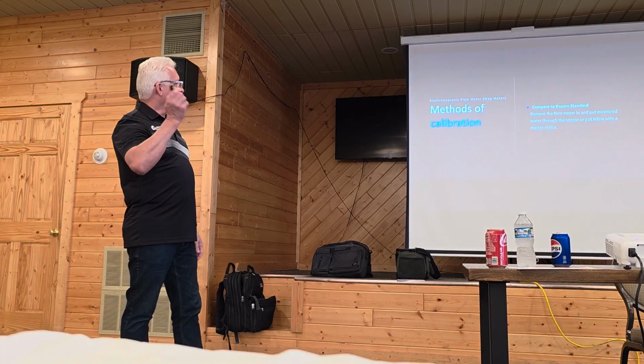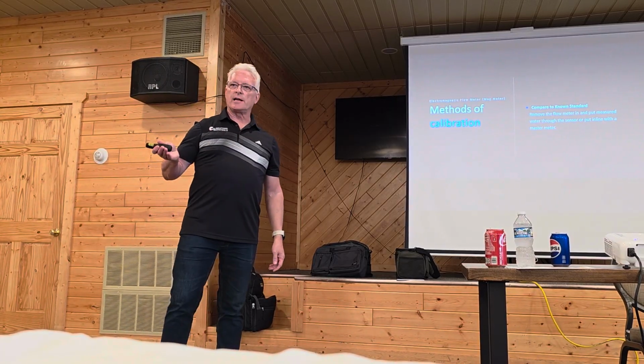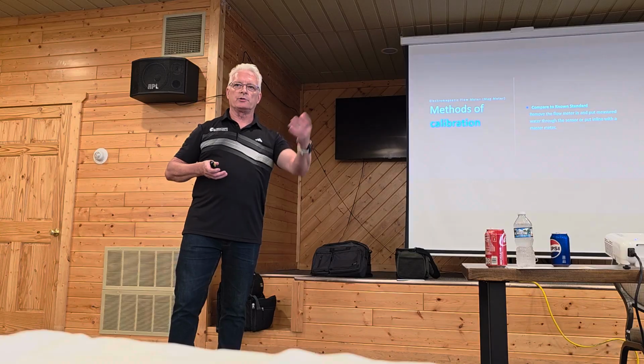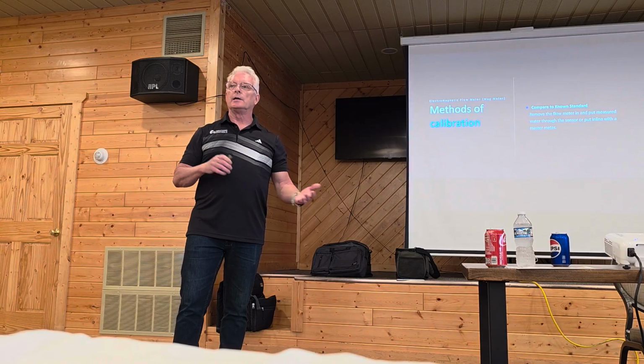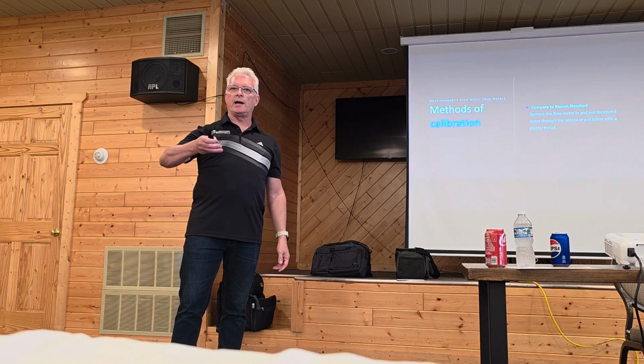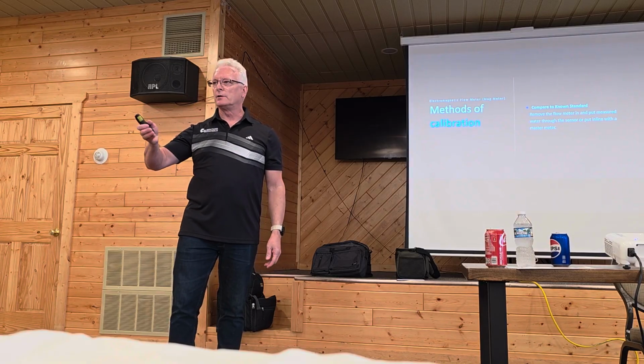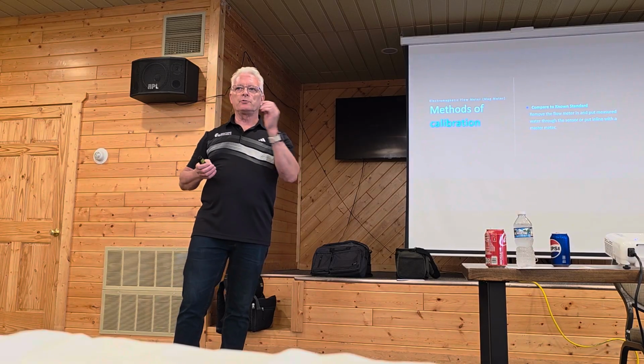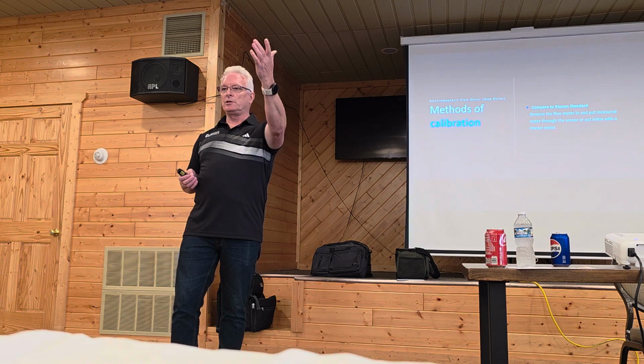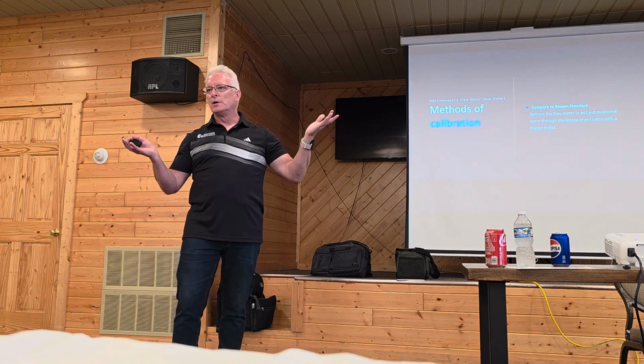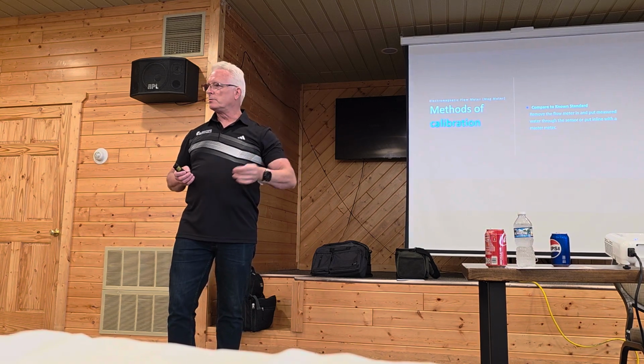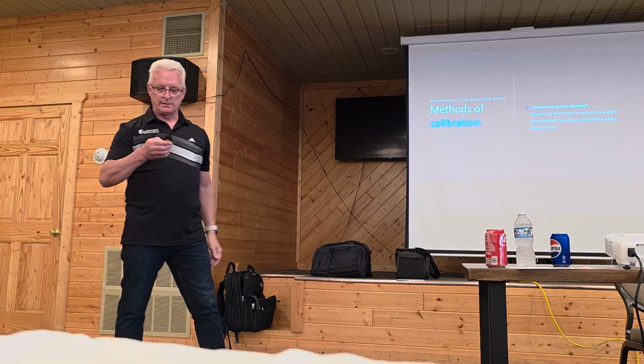Methods of calibration, we already talked about this a little bit, comparing it to a known standard. Like a scale, you put the weight on it, make sure it's right. And if it's not, now you have to calibrate it. If you can't, then you just say it's off by a ½ pound or off by a ¼ pound. Some things you can't change. So then you document what it is. They can change it in their SCADA, PLC if it's important, or you just have notes and then you watch your stuff and make sure it's right.